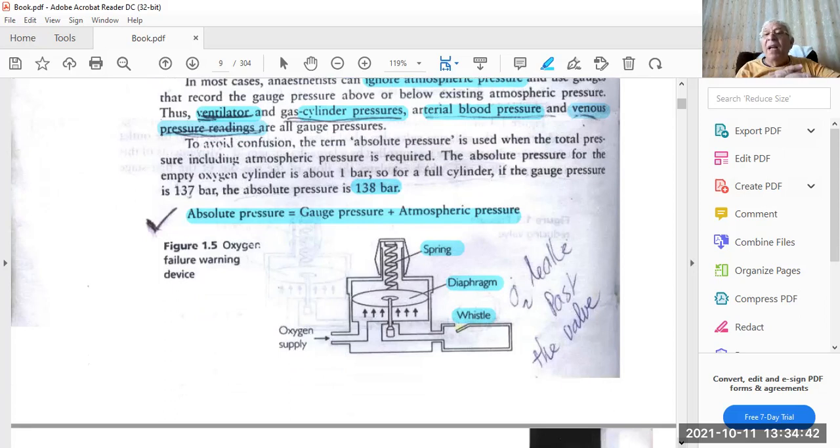as we see from the figure. This is a safety valve in the old anesthetic apparatus. It utilizes the first stage reducing valve. As you can see, whenever the oxygen pressure is decreased, the diaphragm will descend, and the valve will descend, making more oxygen go to the other side by increasing the opening. This will create a whistle. This whistling will remind us that something is wrong with the oxygen pressure.